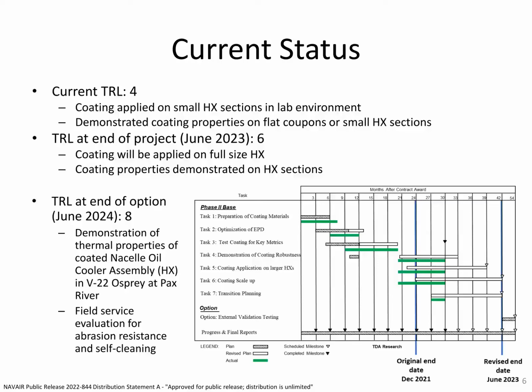This project also includes a 1-year option period, running from July 2023 to June 2024. During this option period, we would demonstrate the thermal properties of a coated nacelle oil cooler assembly by actually putting that coated heat exchanger into a test aircraft at Pax River Naval Air Station. If the coated heat exchanger passes these tests, then it would move on to a field service evaluation for abrasion resistance and the self-cleaning properties.